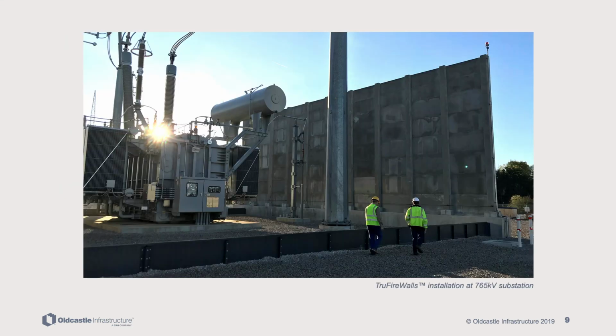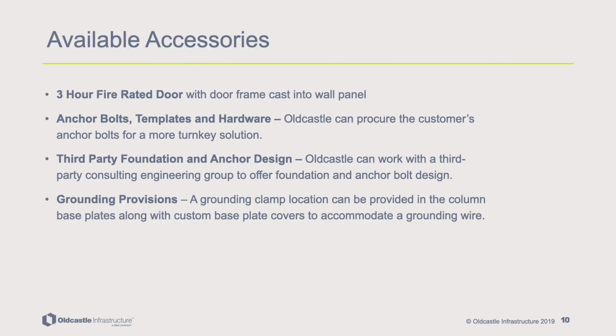Here, a TruFire wall's installation at a 765 kilovolt substation is shown both protecting the substation from external factors, as well as protecting the rest of the site from potential hazards. Both the TruFire walls and Defender walls are available with 3-hour fire-rated doors with door frames cast into wall panels. Oldcastle can procure a customer's anchor bolts, templates, and other hardware, as well as work with a third-party consulting engineering group to offer custom foundation and anchor bolt design for a more turnkey solution. Grounding clamp locations are available in the column base plates, along with custom base plate covers to accommodate a grounding wire.